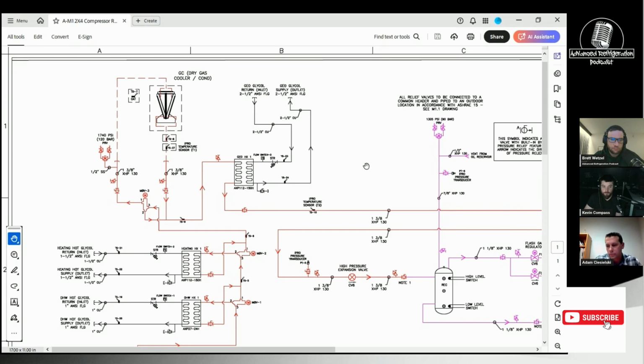Yeah, we've had really good results with it. And then the other part of it, we did it on this rack, is the gas cooler fans are all split up. It seems like a lot of the OEMs or the gas coolers are just sending out everything wired for 1 AO or no cycling. That seems to be a huge issue with all the gas coolers, not having the ability to kill an ECM motor without starting 6 motors at the same time. I understand everybody's trying to build this and get the bid in, but that seems to be a huge gas cooler issue, not being able to cycle fans.